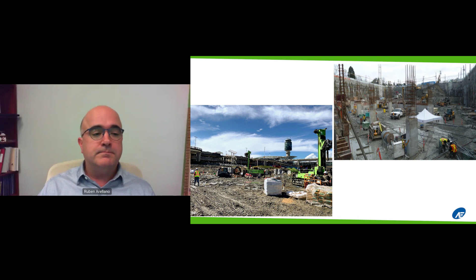And then another definition here is just around wastewater heat recovery. So the concepts are similar to GeoExchange. It's using heat pumps to access a lower temperature source. In this case, it's the plentiful heat in wastewater flows, which can range from 10 to 25 degrees Celsius. And that heat is primarily domestic hot water or process water, clothes washing systems. That heat energy you put into it and use very temporarily is literally just going down the drain and discharged to the environment after treatment.